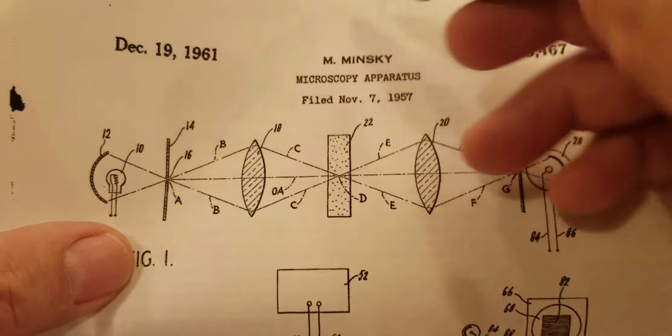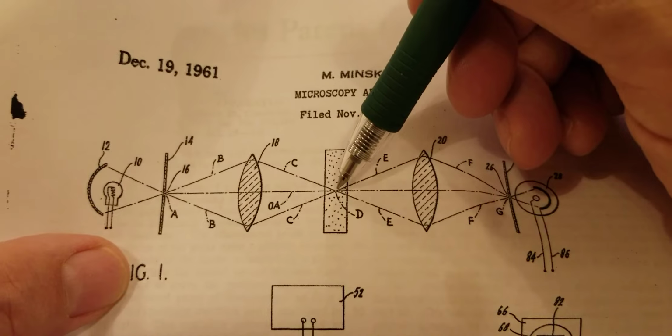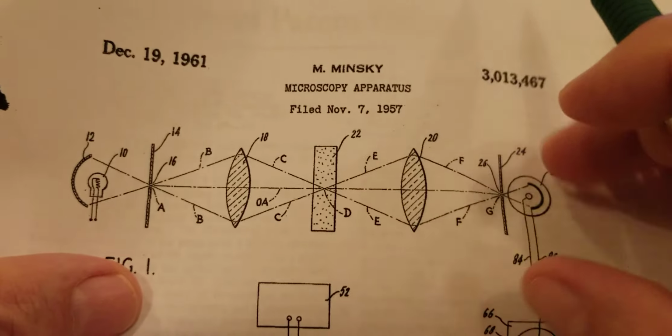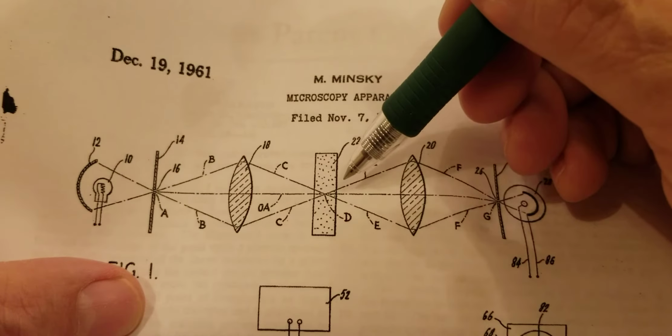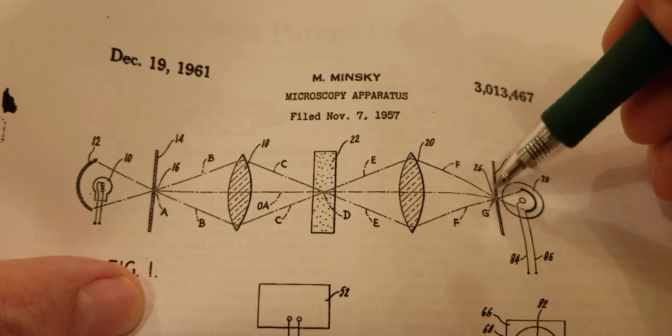This is just the exact mirror opposite of it. This is a photo detector. This lens would focus the light exactly from this spot to exactly through this narrowest of hole, and it would pass through the hole, and then it would go into a photo detector. So we're not focusing an image on this side. All we're doing is looking to see how bright the light is coming from that exact point right there. That's all we're looking for. And the only light that can get to this detector would have to follow a perfect path so that it goes right through this narrowest of hole.